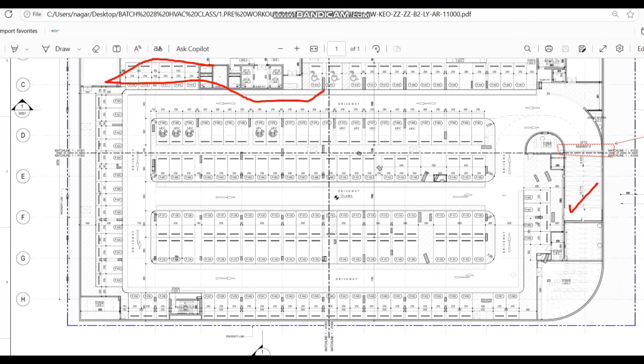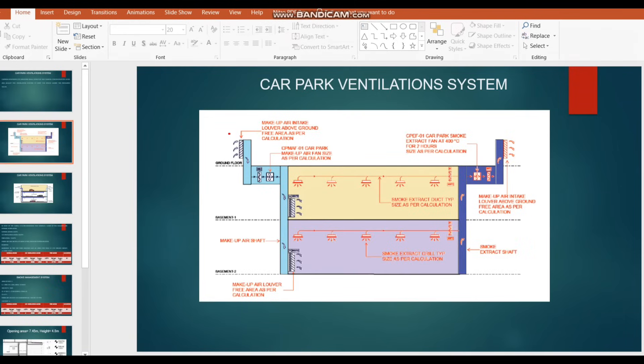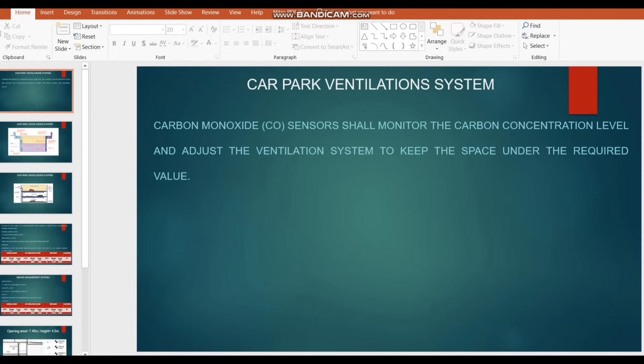With these practical difficulties, we need to exactly size the design. In this video we will see all the practical challenges and how to design a proper car park ventilation system. Simply saying, in the car park system we have the exhaust duct and the makeup air duct. We have a makeup air fan which supplies fresh air to the different basements, and similarly an exhaust arrangement with smoke exhaust grills collecting air through the duct and throwing it outside via the exhaust air louver. The system also has a carbon monoxide (CO) sensor which monitors the CO concentration level and adjusts the ventilation system to keep the space under the required value.